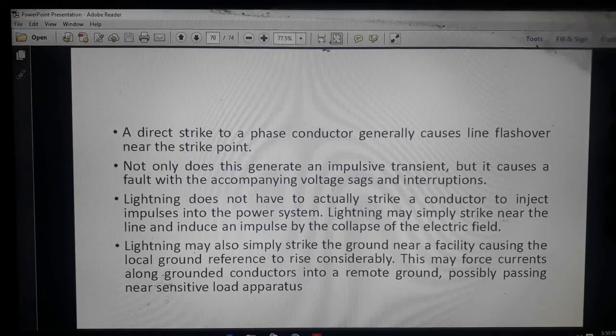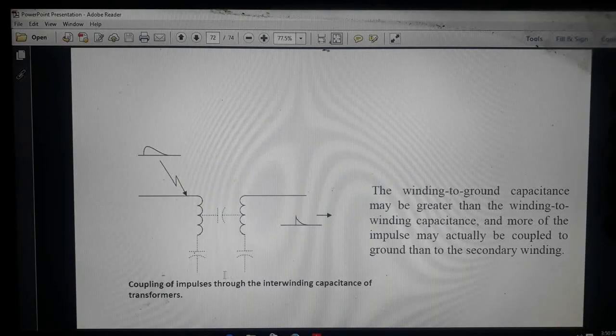Lightning may simply strike near the line and induce an impulse by the collapse of the electric field. Lightning may also strike the ground near the facility, causing a local ground reference rise and forcing current into the ground. Also, the winding to ground capacitance may be greater than the winding to winding capacitance. More of the impulse may actually be coupled to the ground than to the secondary.